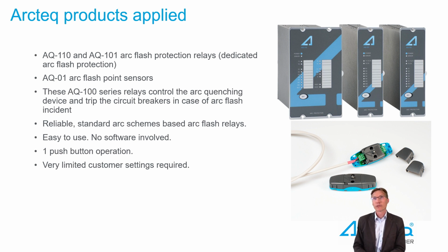And then the actual arc flash protection implementation, with the dedicated arc flash protection units, AQ110 and AQ101 relays, and related arc flash point sensors. Notable here is that all the arc flash protection was separated from the other protection system. So motor protections, feeder protections, transformer protections are set aside. They are on the numerical IEDs, but the most critical and sensitive protection, which is the arc flash protection, is implemented by dedicated arc flash protection relays. So these AQ100 series arc flash protection relays, along with their sensors, control the arc quenching device, and they trip the circuit breakers as well.